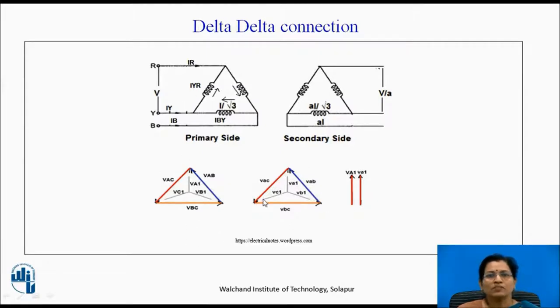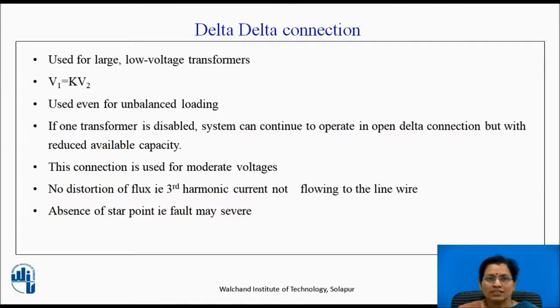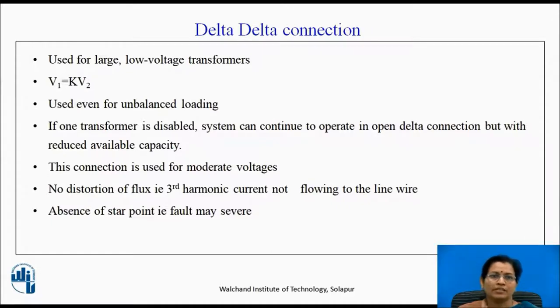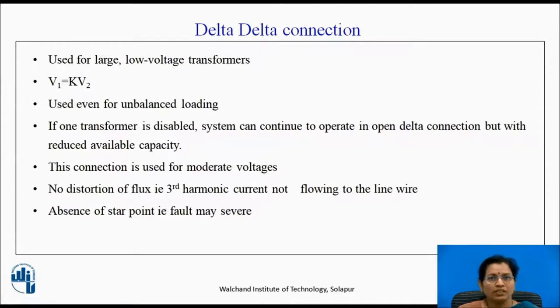From the phasor diagram, both voltages are in phase. If one transformer is disabled, the system can continue to operate in open delta connection but with reduced available capacity. This connection is used for moderate voltages. No distortion of flux — the third harmonic current is not flowing to the line wire. In delta connection, the star point or neutral point is not there, so if a fault occurs, that fault may be severe.